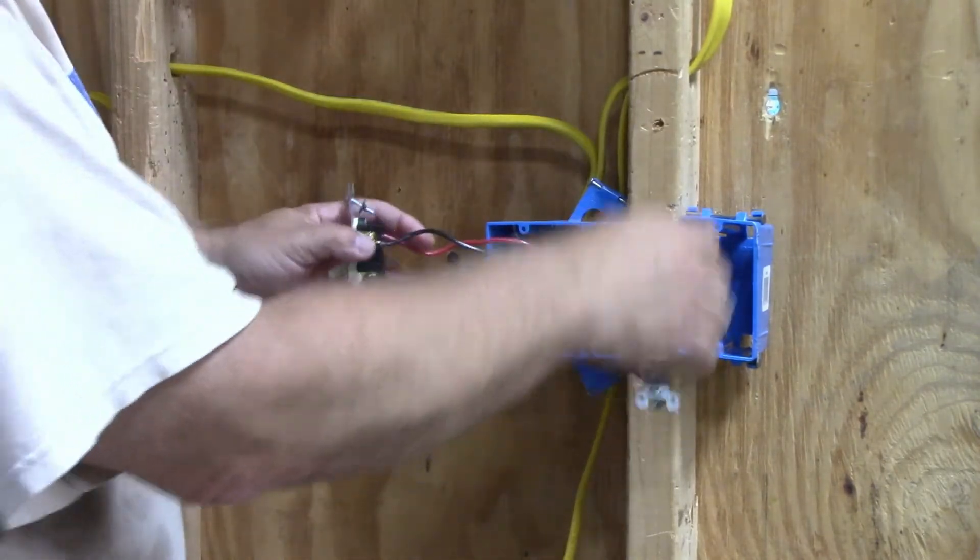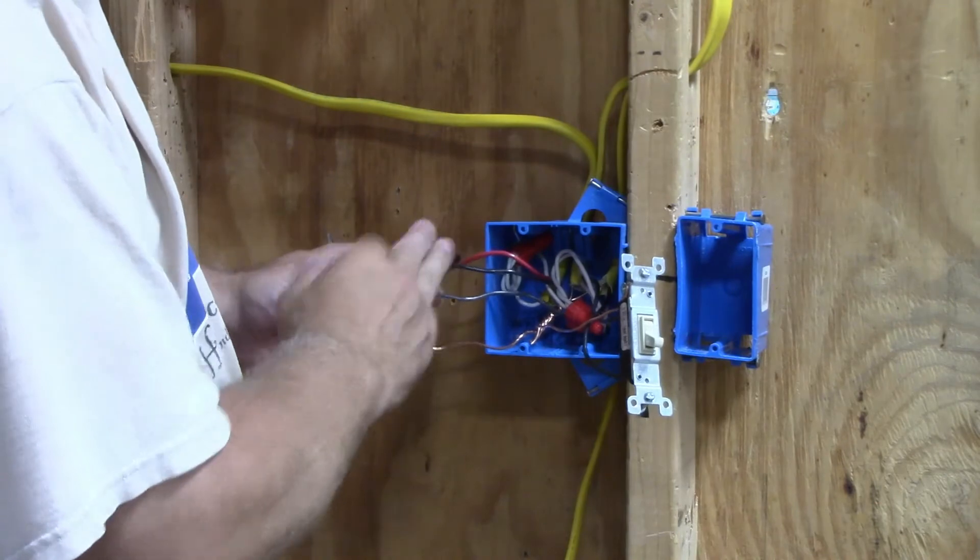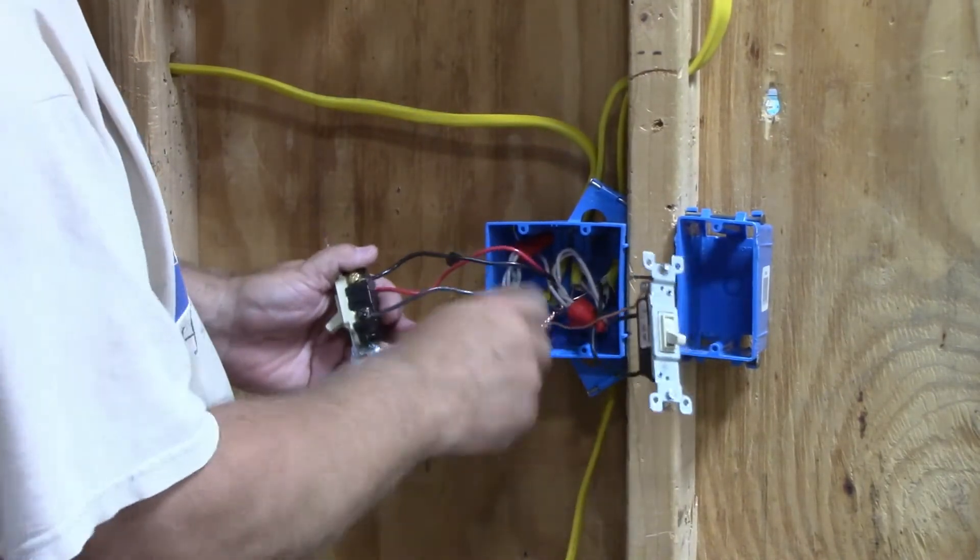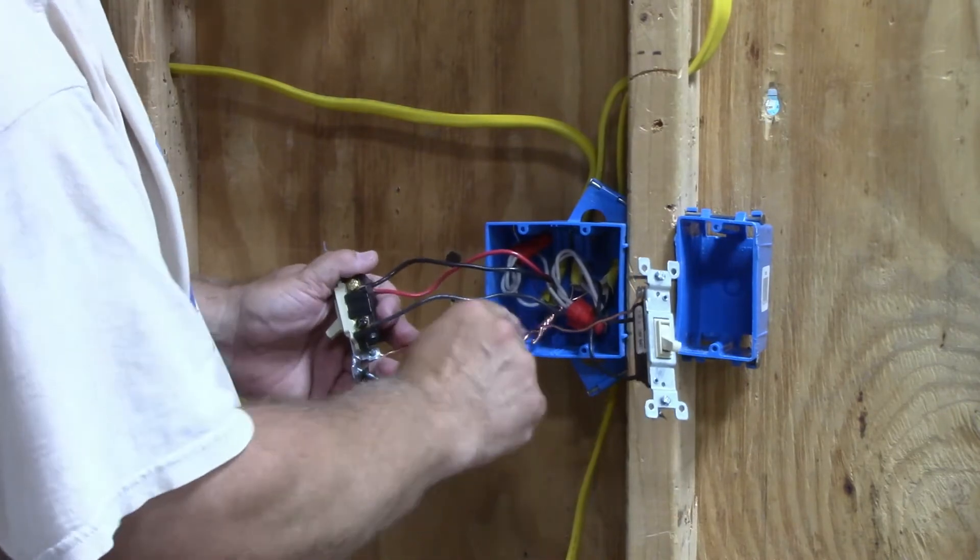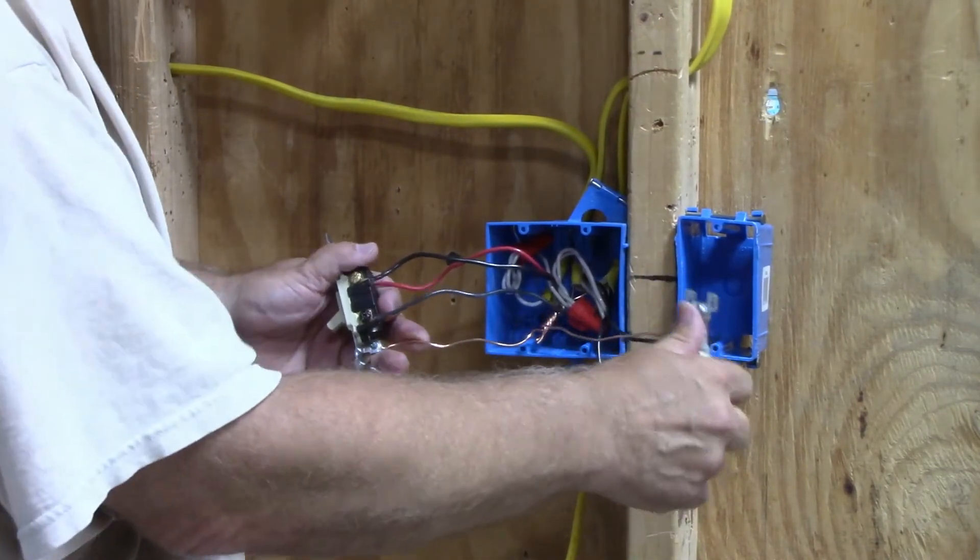A single pole switch running a light on a separate circuit than the three-way switch. What do you need to remember? Number one, all your ground wires can be hooked together. I twisted them all nice and tight so I don't have an open ground. One goes to the single pole switch. One goes to the three-way switch.